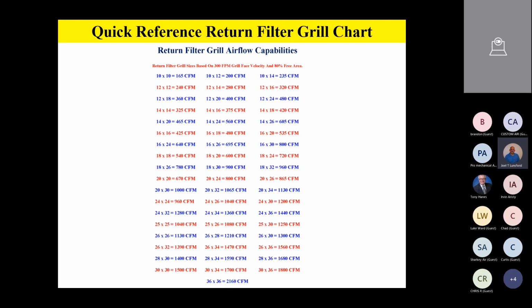But if you start getting down below 350, especially if it's high static pressure, it's going to be noisy, and you're not going to be able to handle humidity like it should. But yes, to both questions, it'll give you reduced capacity and a reduction in humidity control. And remember, guys, the larger the duct, the lower the velocity and the quieter the system. Now, you don't want to get too large, but there are target velocities in those duct components that we will certainly talk about in our airflow class. This is just how to measure airflow today. Excellent question, though. Any other good questions or comments?